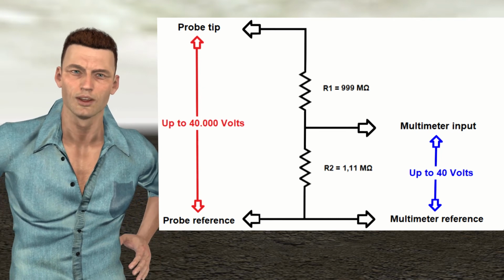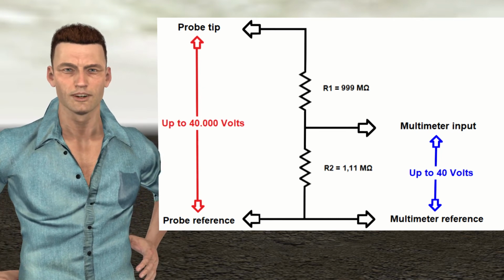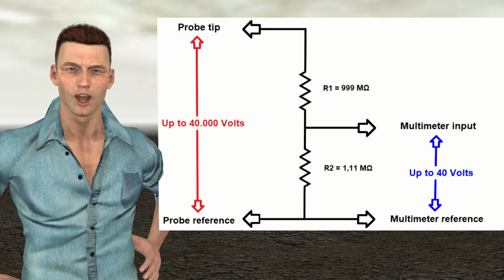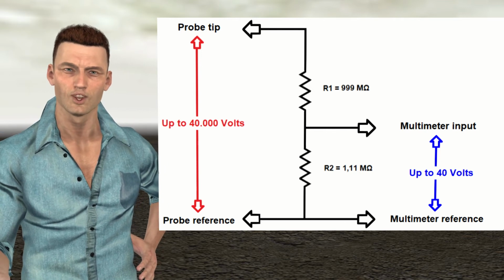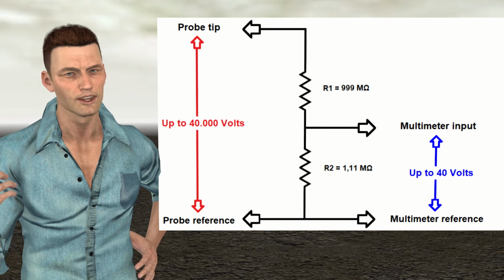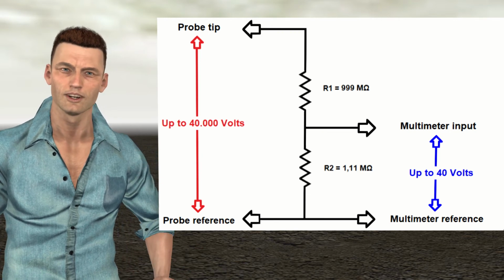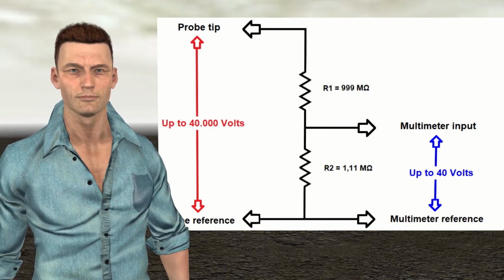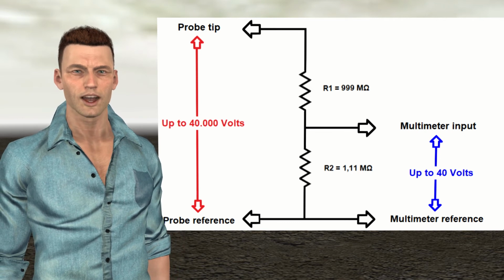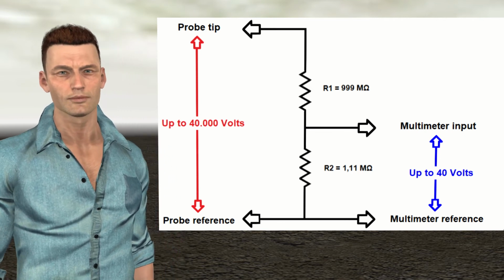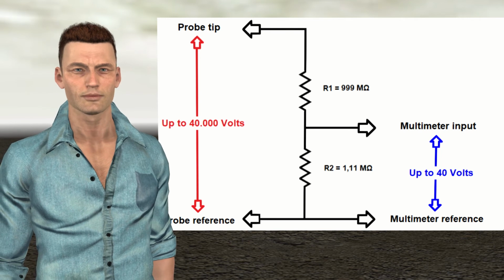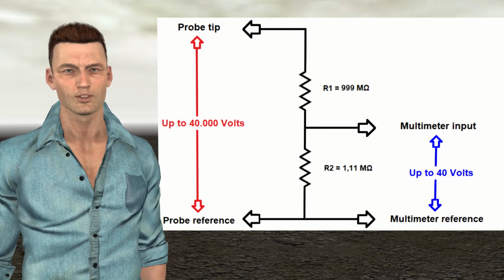In case the multimeter has a different input impedance, then the indicated ratio of 40,000 to 40 will not be correct, and an additional correction factor must be applied. If, for example, the multimeter has an input impedance of 1 mega-ohm, the value shown on the display should be multiplied by 1901, instead of by 1000, to obtain the correct high voltage value.